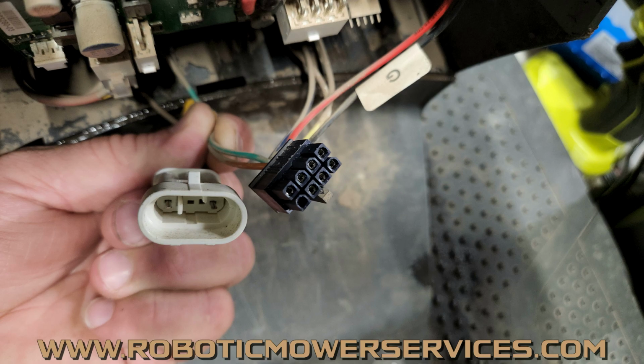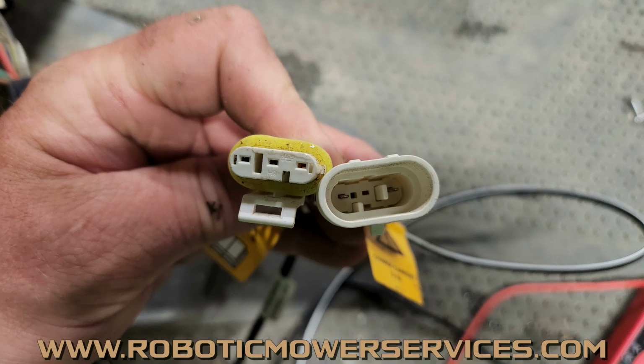You know that your charging station harness is good. If you do see a bit of resistance there in either the positive or the negative side when you're checking that entire loop, then you can unplug the low voltage cable from the charging station. Test it individually. Test from the back of your charging station to that plug in the front that goes in the circuit board. See which component has the resistance buildup. Maybe it's both of them. It's hard to say until you actually test it.